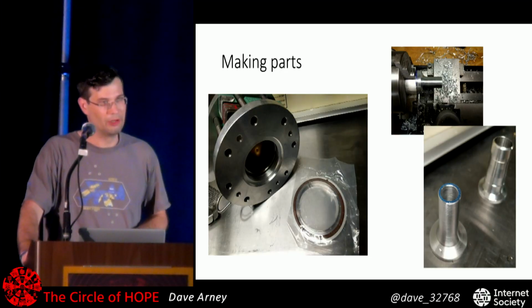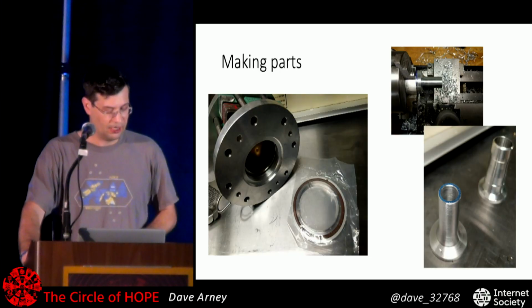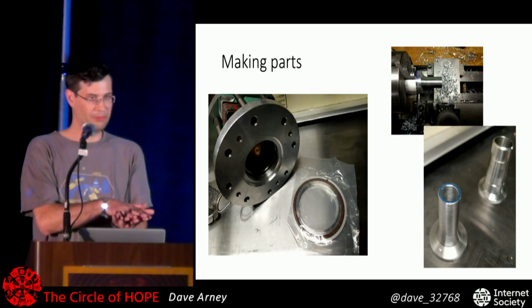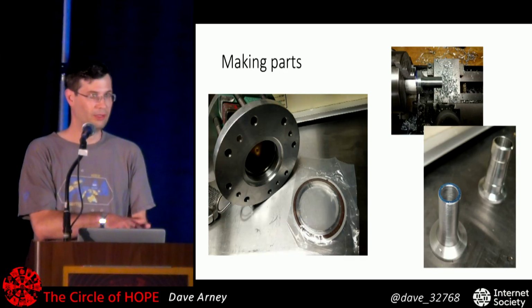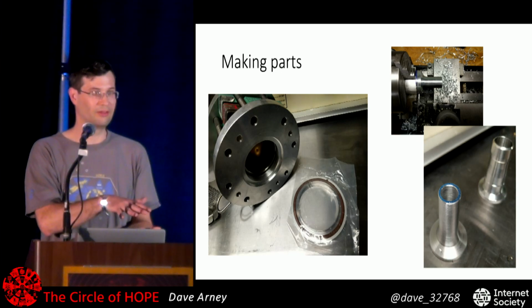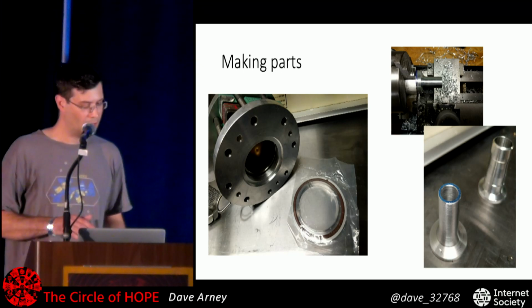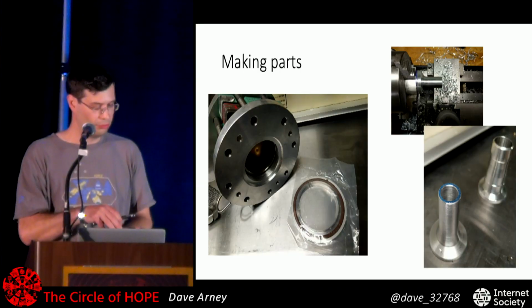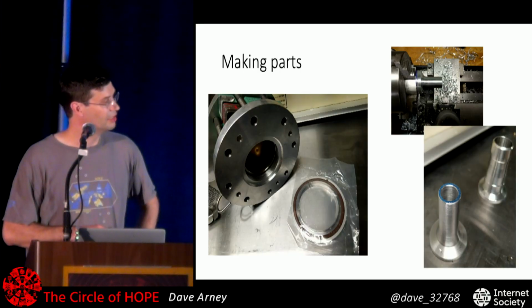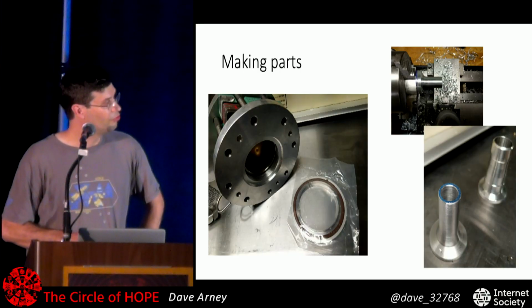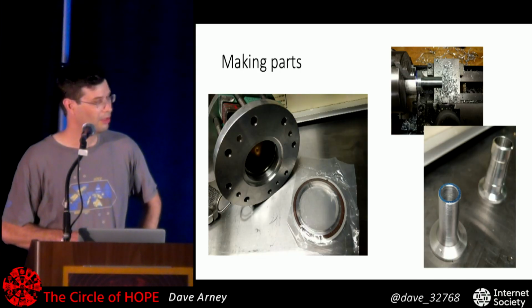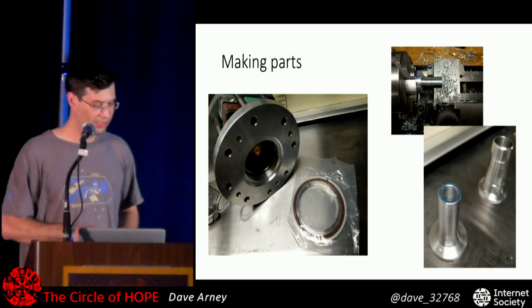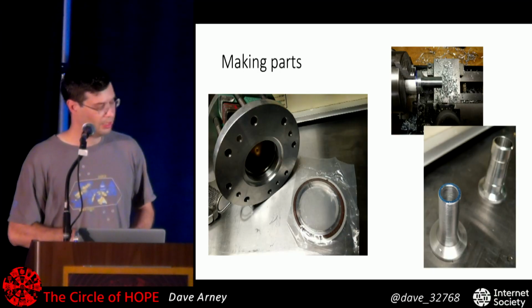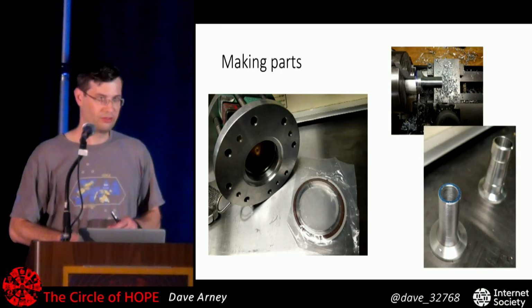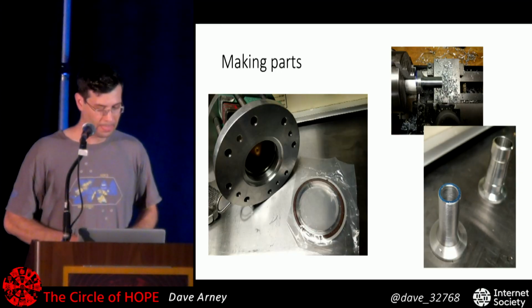They come in different diameters, with a few standardized sizes. You put one between your parts and clamp them together with enough force to compress the O-ring. When you pump your system down, it gets further clamped because of the vacuum, and that's enough to hold everything together and keep it airtight. These are really nice to work with because all you have to machine is a groove big enough for the metal inner ring to sit in, and a flat surface for the O-ring to sit on — an easy way to build pieces and connect them together.